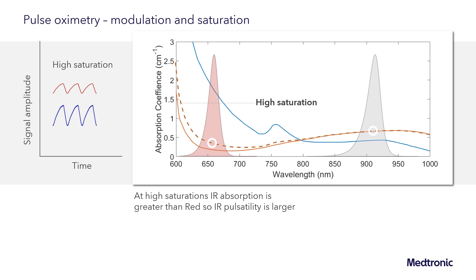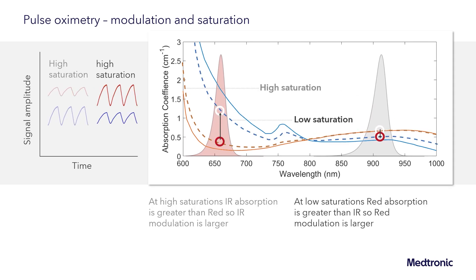Going back to the absorption spectra of blood, at high saturation where the blood is primarily oxygenated, we have low red absorption — resulting in a low percent modulation of the red — and higher infrared absorption, giving a higher percent modulation of the infrared. As that blood desaturates and goes to lower saturations, the red absorption increases, resulting in a stronger modulated signal and a higher percent modulation, while the infrared signal decreases, resulting in a lower percent modulated signal.